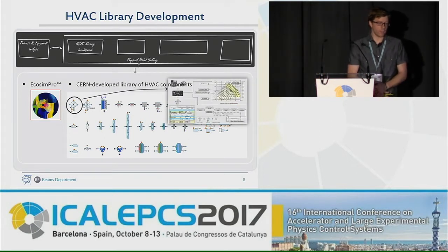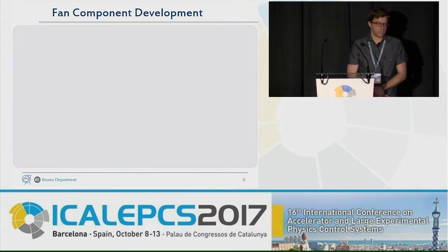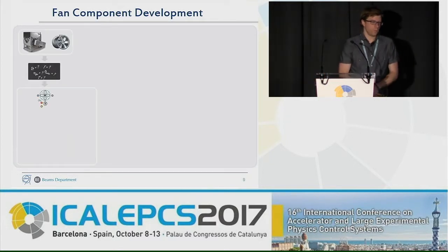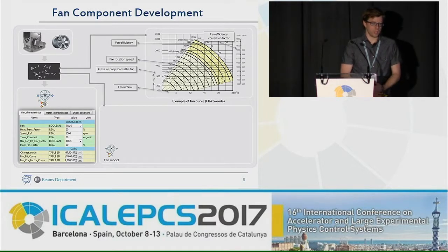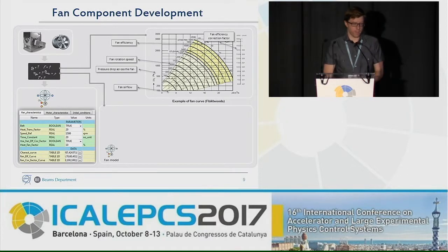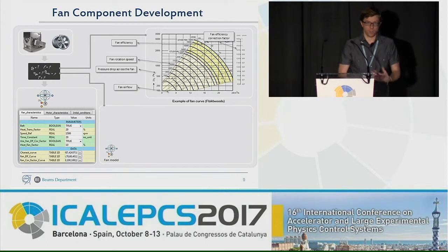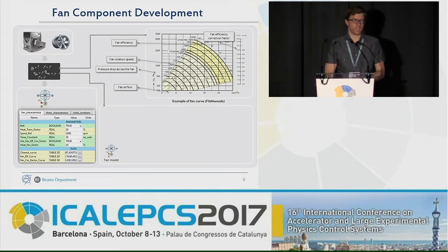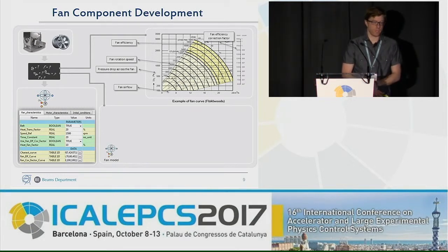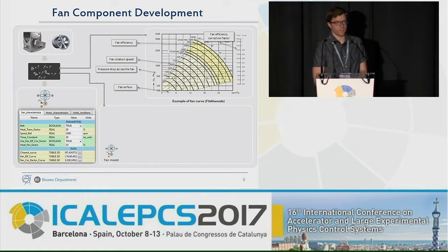So zooming in on one, this is a fan. To give you an example of the detail, we look at the corresponding fan curve that can be entered. You take it from the supplier data sheet showing the correlation between pressure drop and airflow. You also have the data related to rotation, fan speed, and fan efficiency.